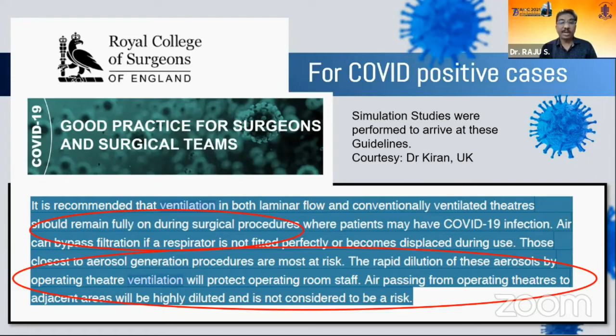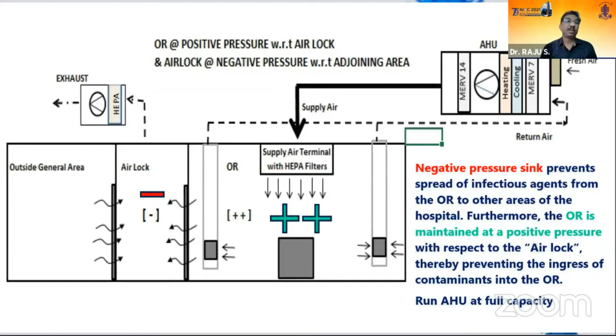However, if at all we want to add a negative pressure, we can do it without modifying the existing OT by adding what is called an airlock. If you have a room adjacent to the OT, a negative pressure sink can be created to prevent the spread of infection. What is basically done is, in the adjacent room, a powerful exhaust with a HEPA is added. This will suck the air out of that room. The OT will continue to be at positive pressure, and the adjacent area will also remain the same. And this negative pressure sink will prevent the infective air from the OT getting onto the general outside area.